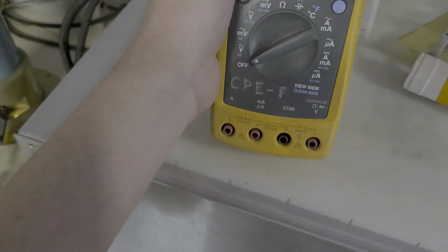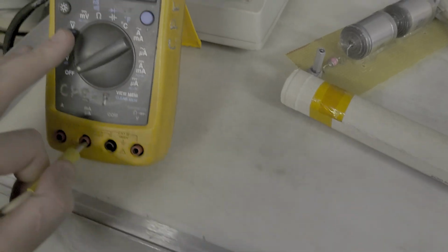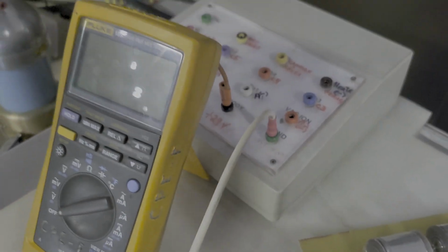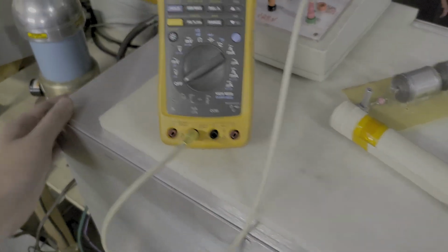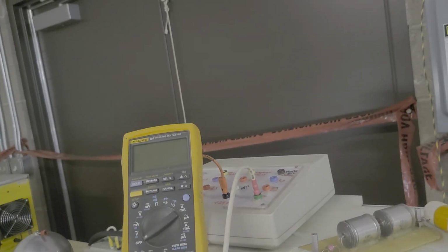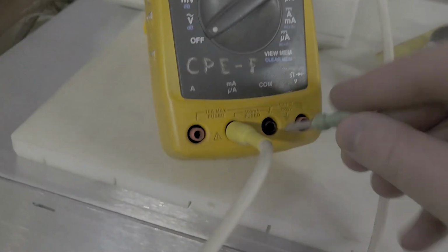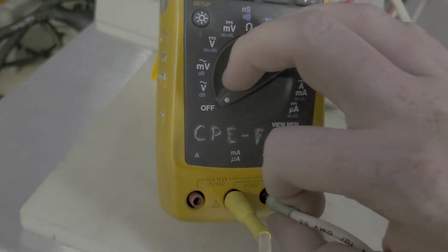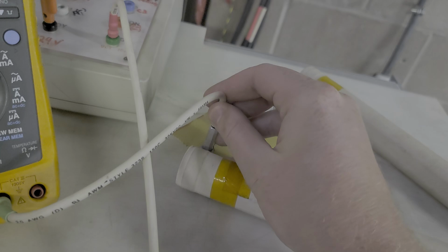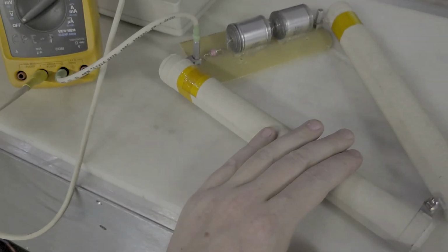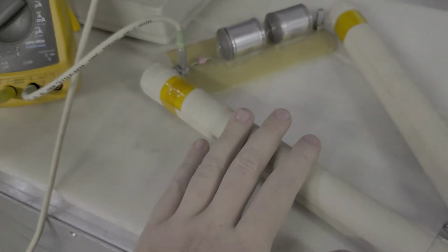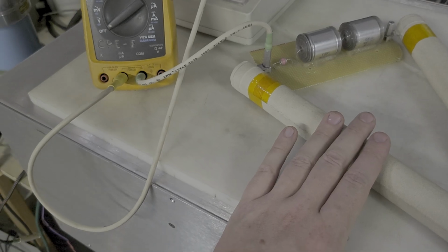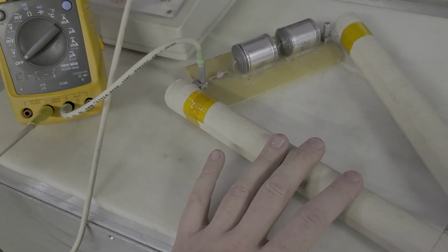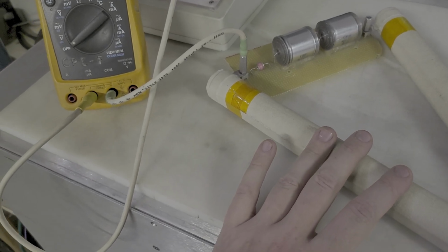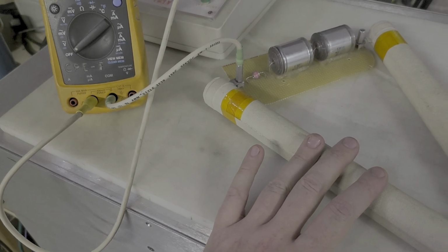Let's grab our handheld multimeter. And we're going to wire the multimeter to the ground lug of our breakout box. This is earth ground chassis, okay? And the other side of the multimeter, we're going to wire to the bottom of our load. Now they can pick out the load that they need to run the current they want. The Helix will run up to 20 milliamps. So if they need something higher, they'll need to create a lower value load. This one I think runs at around 8 milliamps or so maximum.